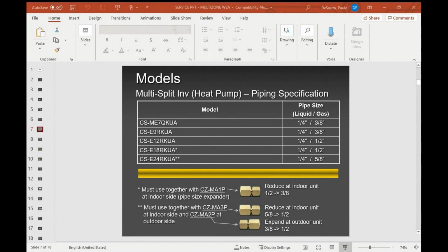Okay, guys. We definitely have some minor issues, but as long as you can see what I'm explaining to you, that's the main thing, guys. So like I said, with other manufacturers, you will run the pipe of the indoor unit all the way to the outdoor unit and then rectify at the outdoor section. In our case, it's the opposite. You run 3/8 and quarter all the way to the indoor unit. And when you get to the indoor unit, in this case, for example, if we use a 12,000 BTU unit, you will upsize it to 1/2 inch. The quarter remains the same, the liquid line. But the 1/2 inch, you will use an adapter and you do your connections and you're good to go.